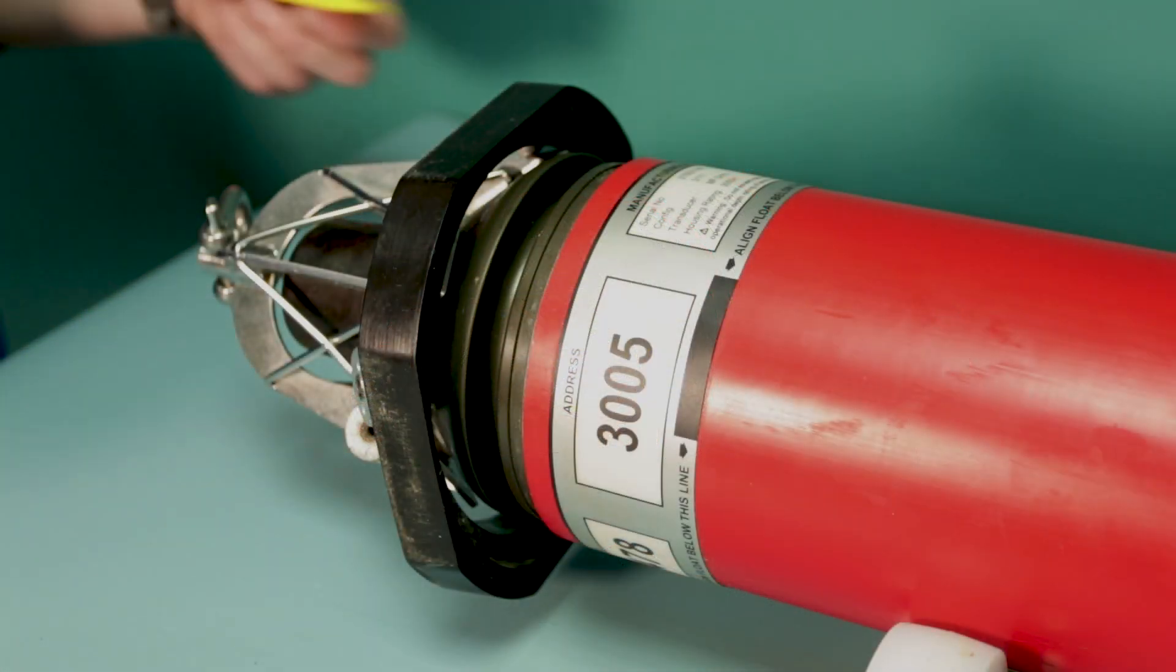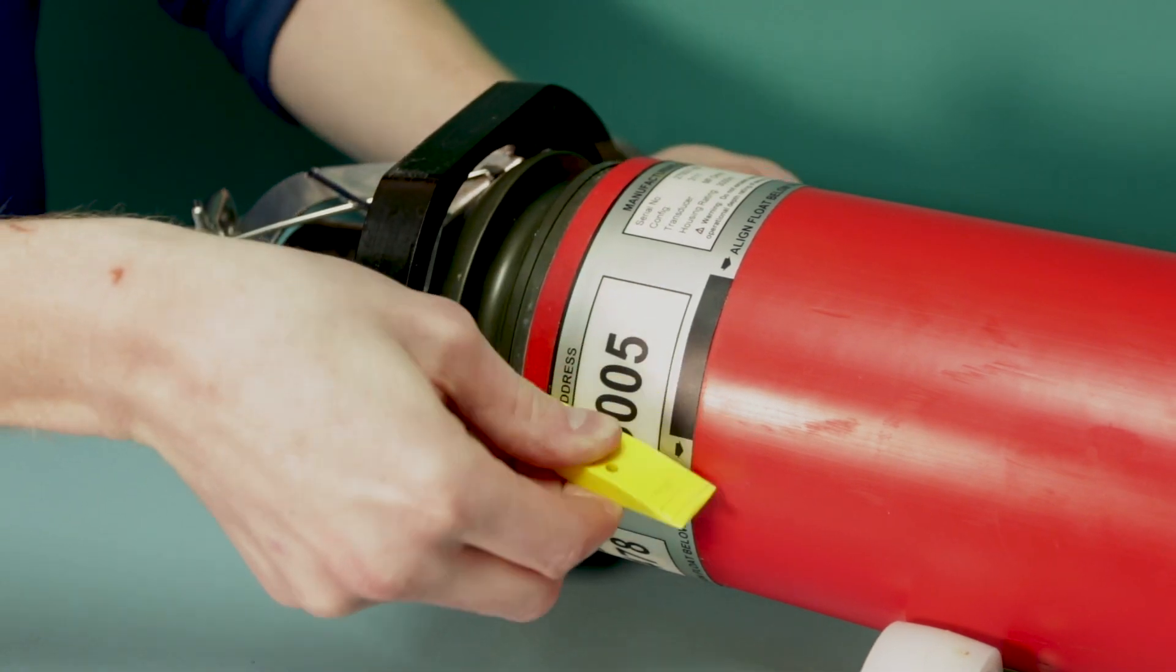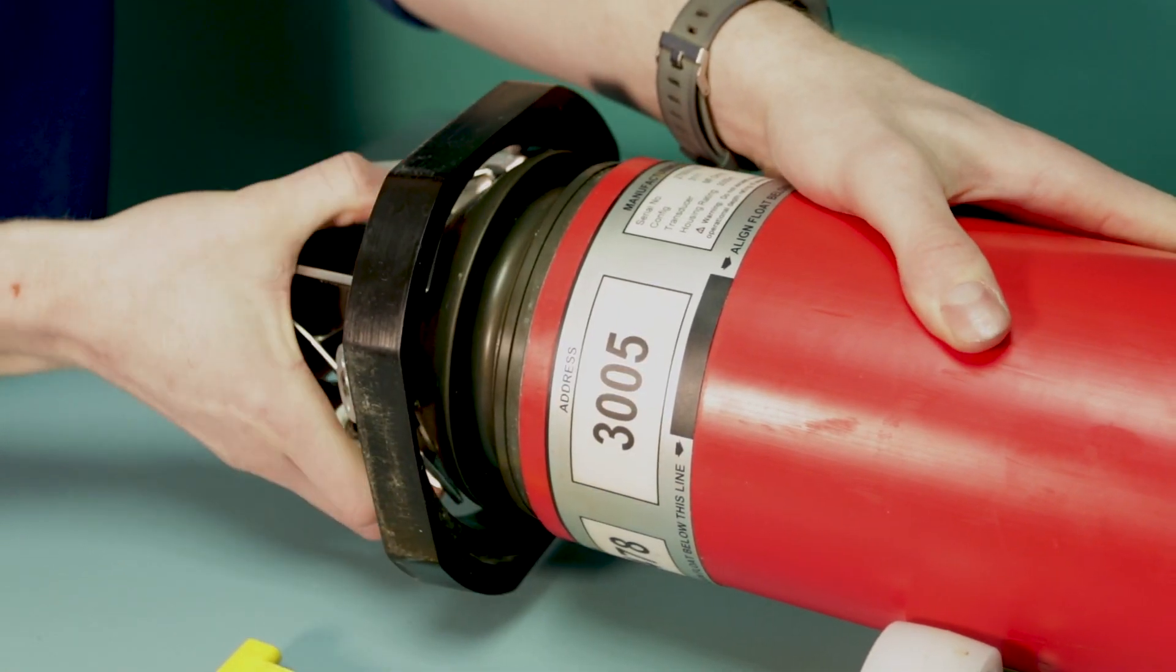Using the yellow opening tools, lever the end cap from the body until both o-rings are visible. Ensure that the o-rings are not caught or damaged during this process. Then gently remove the end cap, making sure not to pull so hard that the transducer connections come loose.